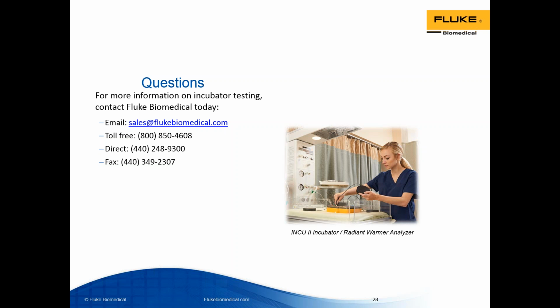Great. Next question. Is an infant incubator a life support device? That's a great question. And to be completely honest, it truly depends on who you ask. So as for the U.S., we go by the FDA. The FDA is kind of the rule and the law of the land. And the FDA says no, that incubators are not considered life support devices. However, if you consider what a life support device is, which is that without the existence of this device, the patient would then undergo unnecessary harm and/or death and would not be able to survive. And again, going back to these premature and sick patients, one could very well argue that without the incubator there, the patient wouldn't be able to survive. So it depends on how you look at it, but according to the FDA, no, incubators are not considered life support devices.